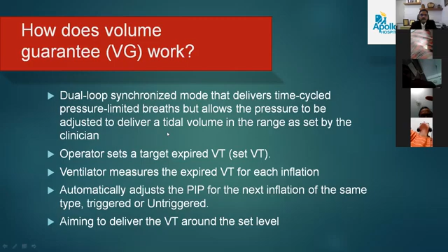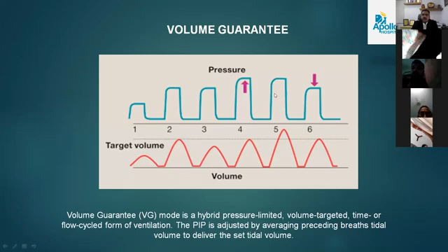Yeah. See, now suppose you have a target volume. Let us assume that you have set a target volume of 6. So when it is reaching this level, it means it is the optimal target value. Now the pressure remains the same. Now in this breath, the target volume has reduced. So immediately the computer senses it, because it has the expiratory tidal volume and it has already calculated that in the next breath the pressure should go up. Similarly, here the tidal volume crosses what you have set. So immediately for the next breath, it reduces the pressure. When this is applied systematically over a long period of time, this inadvertent excess volume or excess pressure would be avoided, and this would be very safe for the babies.